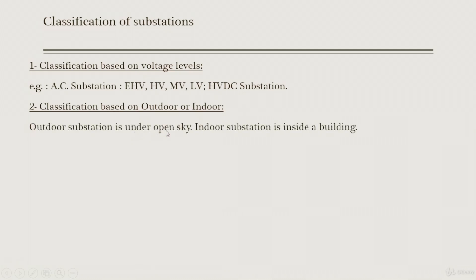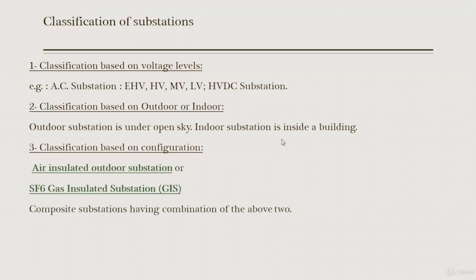The second classification is based on outdoor or indoor installation. A substation can be outdoor — under the open sky in a large open area — or it can be an indoor substation inside a building. We can also classify substations by configuration: air insulated outdoor substations (AIS), SF6 gas insulated substations (GIS), or composite substations combining both.